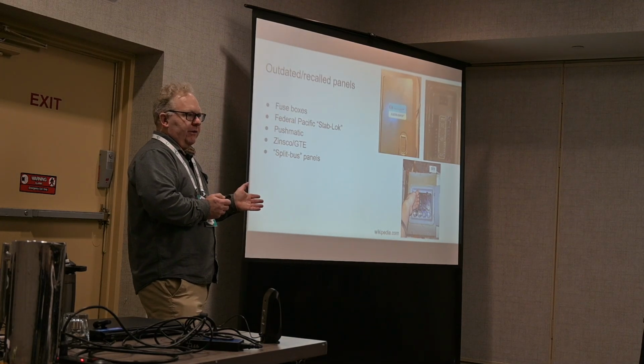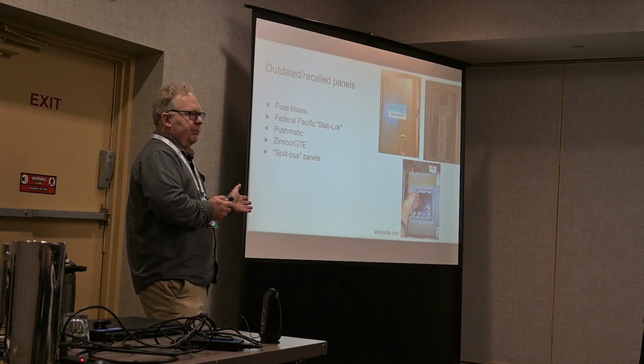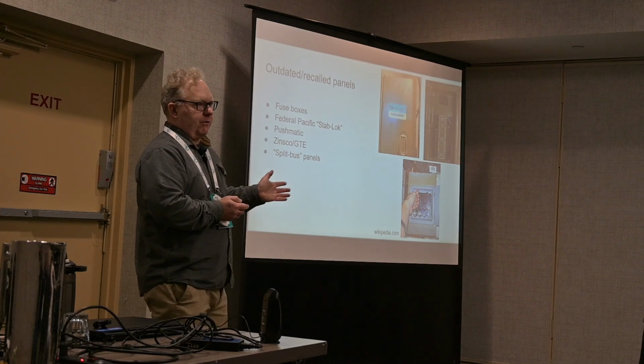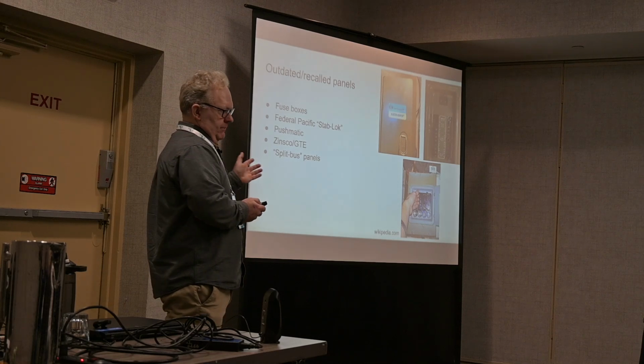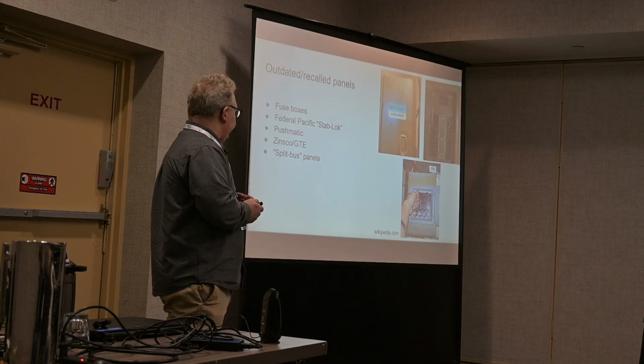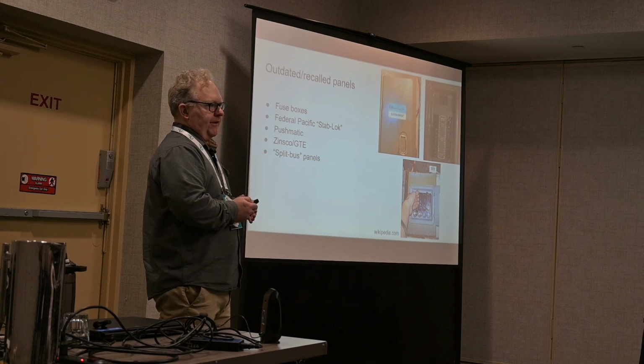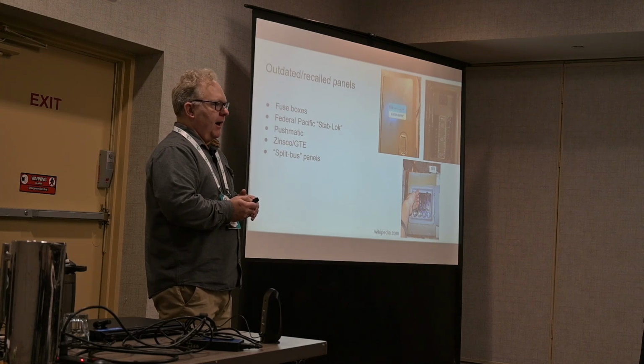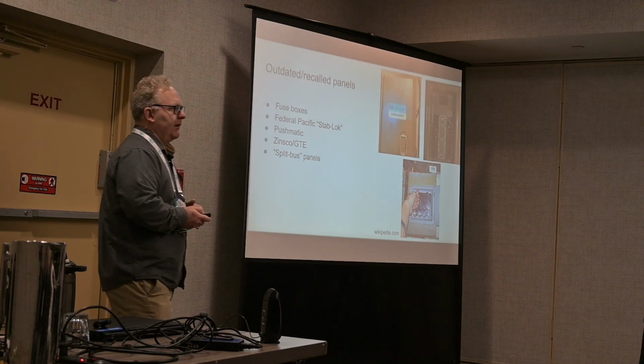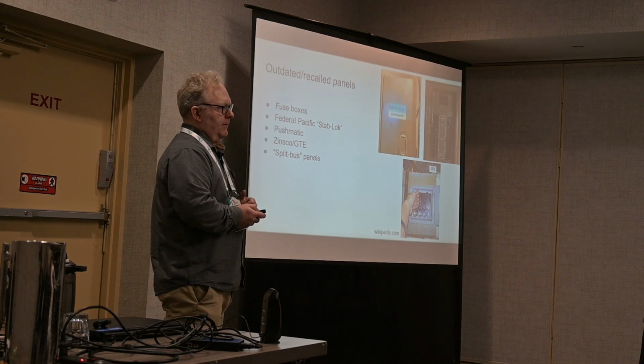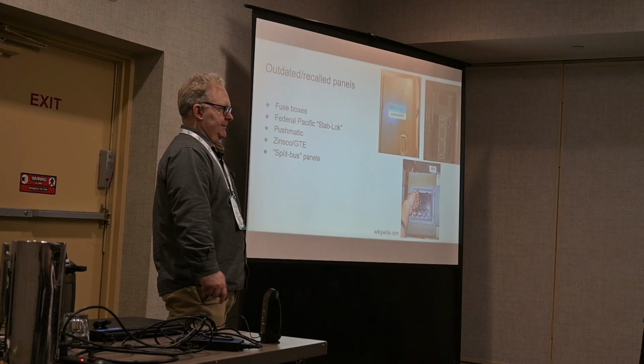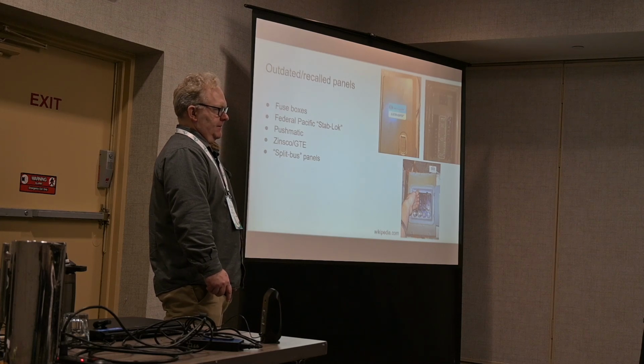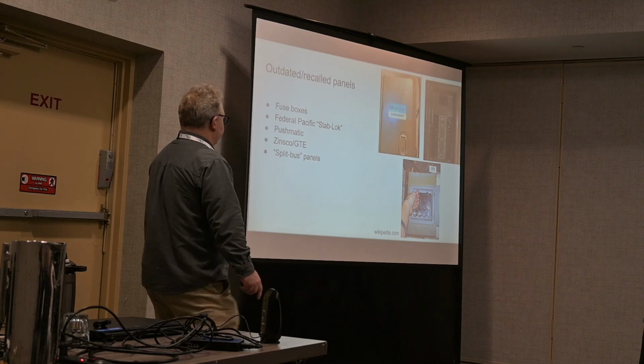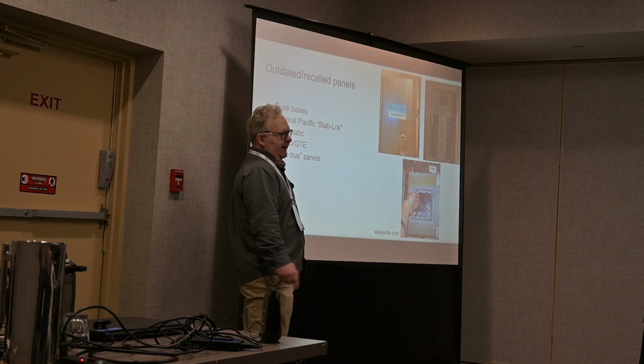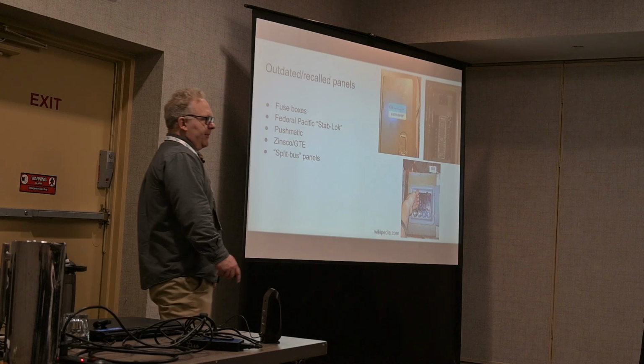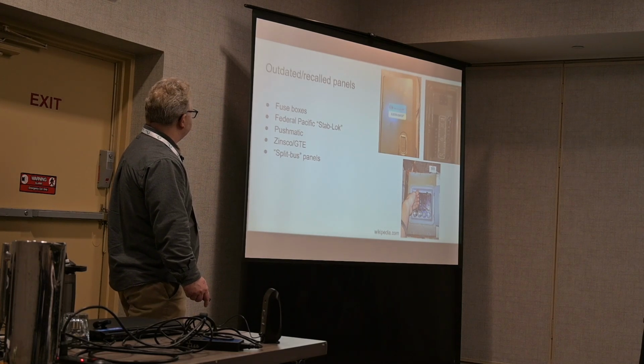Those, I think, don't necessarily need to be automatically upgraded, but you should be aware that they're not considered great to have because there's no main breaker to shut them off, so they don't have that important safety feature. In not having availability for new breakers, so if you're adding heat pumps of any sort, you can't get hands on breakers. Exactly. So that's another consideration. If you run into any of these brands, you might not be able to find what you need.